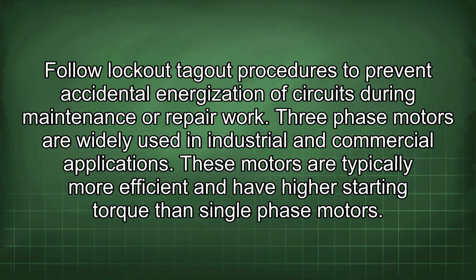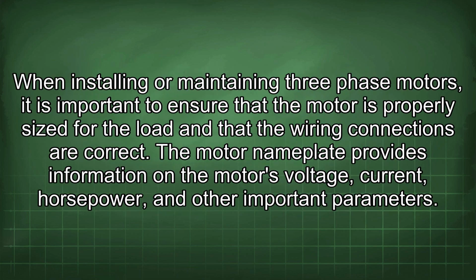Three-phase motors are widely used in industrial and commercial applications. These motors are typically more efficient and have higher starting torque than single-phase motors. When installing or maintaining three-phase motors, it is important to ensure that the motor is properly sized for the load and that the wiring connections are correct. The motor nameplate provides information on the motor's voltage, current, horsepower, and other important parameters.